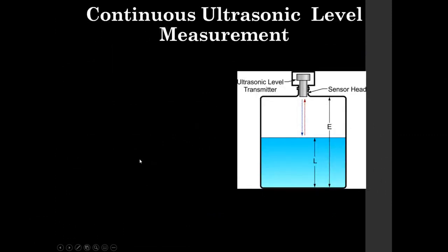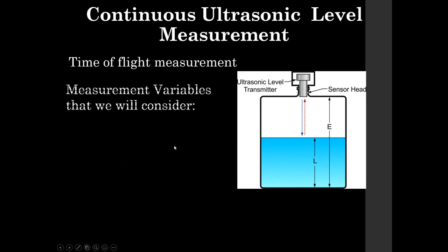Okay, so looking at continuous ultrasonic level measurement here, standard application where we have a vessel and a transmitter mounted on top. The science behind ultrasonic and also radar is called time of flight measurement, again, which is basically saying how long does the signal spend traveling. And so there's a few variables that we have to consider if we look at the diagram of the tank here and the science behind it.